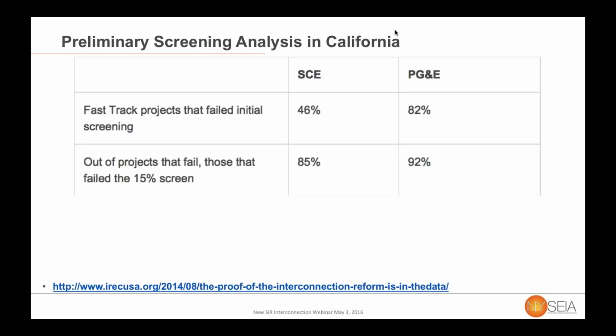So to give you a sense of how important this is, a couple of numbers that IREC pulled from data in California. This is looking at the first couple of years after California updated their screens to include the supplemental review that we're going to talk about. And what they found is that for the two utilities, somewhere between 46 and 80% of the applications were failing the initial review, failing the initial screens. Of those, somewhere between 85 and 90% were failing because of that 15% of peak load screen. So this is obviously a very important screen to take a look at.